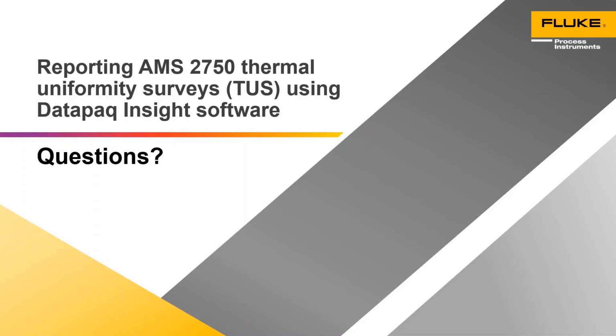As Rob mentioned in the presentation, the best way to record the location of the thermocouples is in the probe map area of the reporting section, and I would very much encourage individual photographs of the probe locations. It's worth noting that you probably need to record the furnace control thermocouple location as well, and potentially load thermocouple locations.